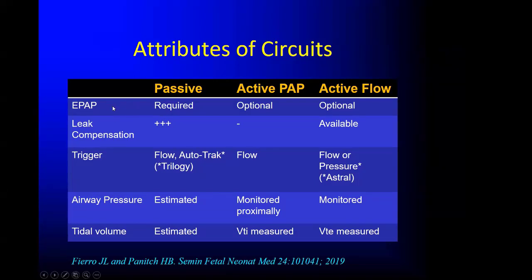And so we have to use an expiratory pressure in order to get continuous flow past that dead space to wash out CO2. When you use either the active PAP or the active flow circuit, you don't necessarily need to use an expiratory pressure, and that may be something that's more comfortable for your patient and a reason that you choose one of those circuits. The passive circuit really is king when it comes to leak compensation. Neither of these circuits does that very well. I wrote here available for the active flow, but that's really for the inspiratory triggering, not so much for delivering a breath.